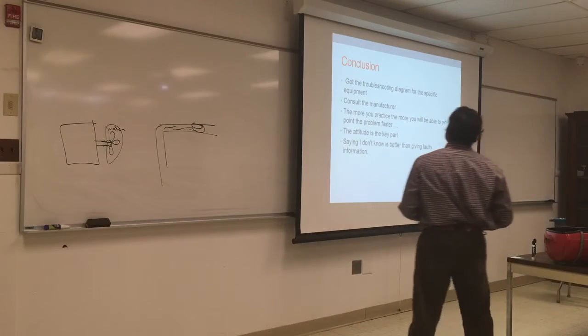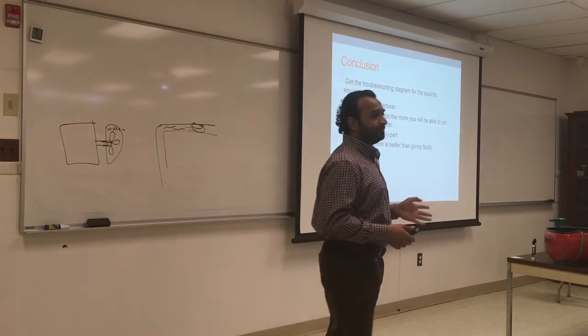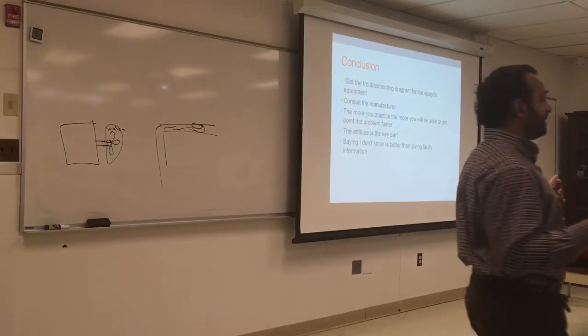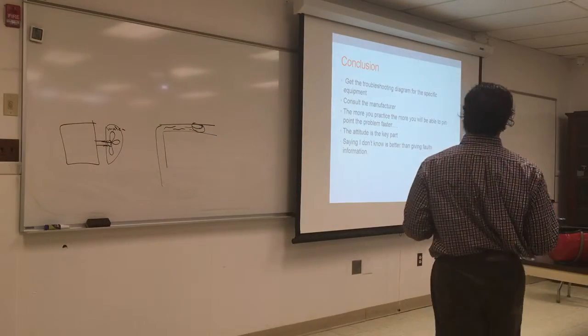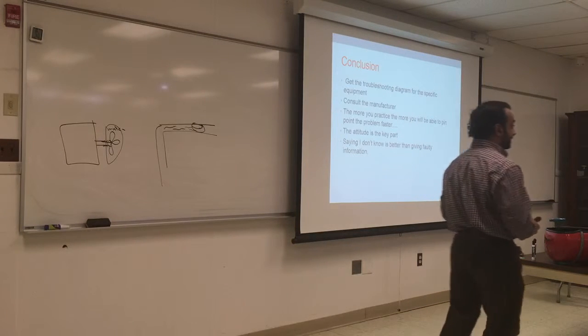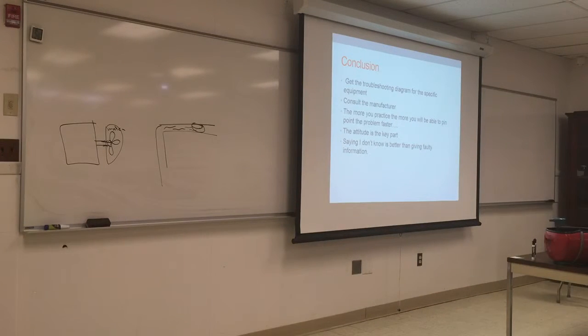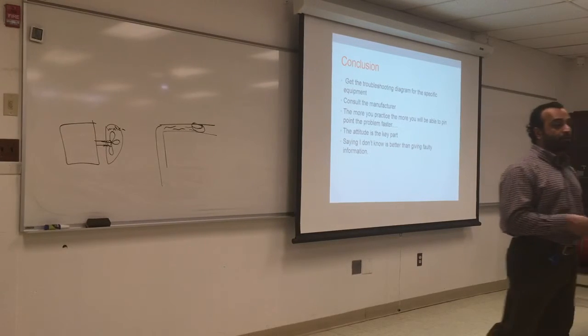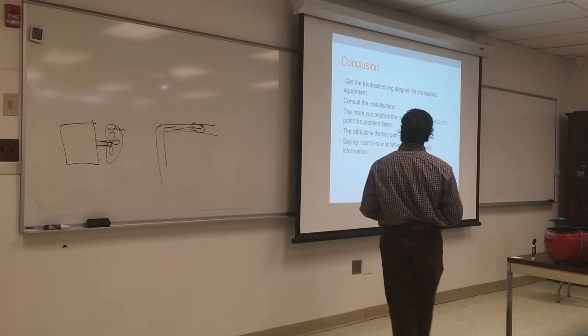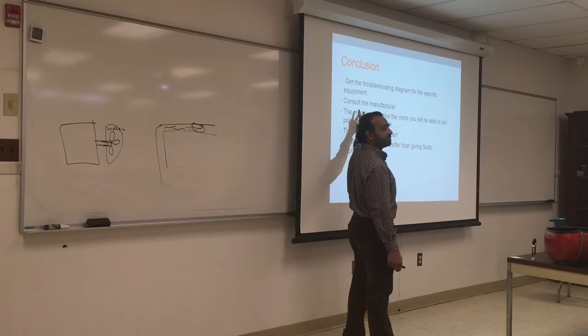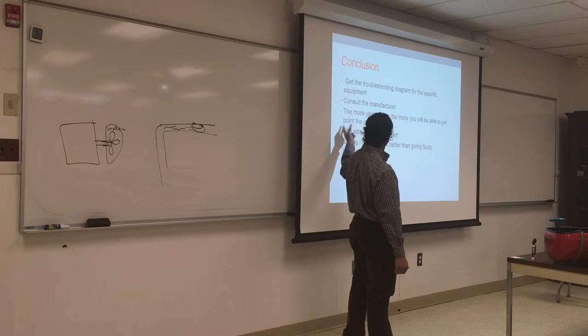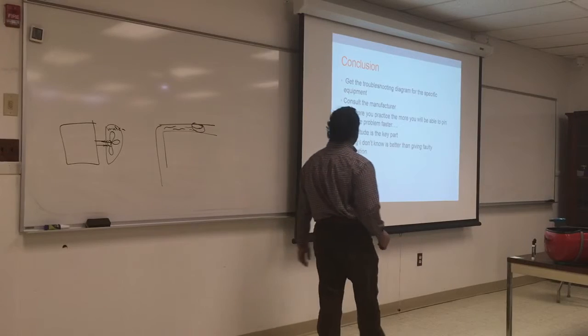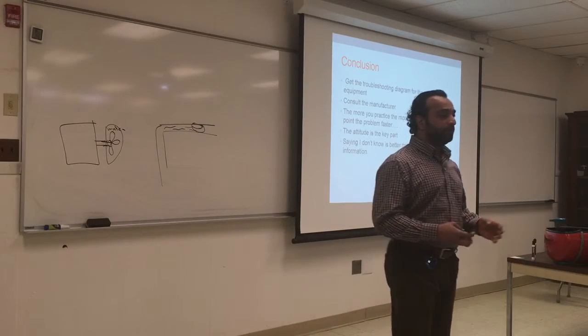So in conclusion, you have this diagram. I gave you a sheet of the copy back and forth with the no heat coil. This could help. In the beginning you will use this a lot, but within a few months of doing this, you will start to have a sense of what could go wrong. And those are built with experience, and always remember that the parts are always going to be the same. When in doubt, consult the manufacturer, especially if the equipment is new. Call and say, this is shutting off for safety, this is leaking, is this normal, what's happening? Sometimes there's a recall. The more you practice, the more you'll be able to pinpoint the problems.